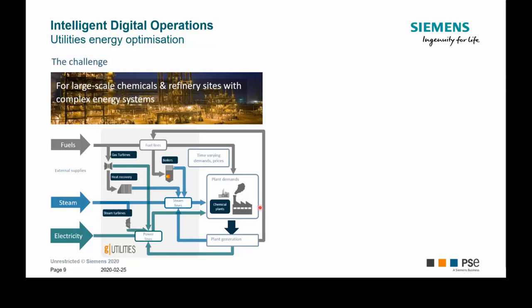Another important aspect when dealing with utilities is the operation strategy. There are several strategies: a long-term strategy covering years, short-term tactical planning covering months, or a daily strategy — which requires dynamic optimization. Saving targets are typically 2–3% for well-operated plants, and 5–10% for not well-managed ones, representing a return of investment of 9–12 months.